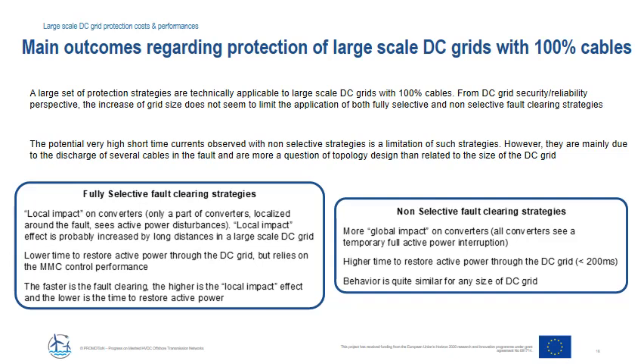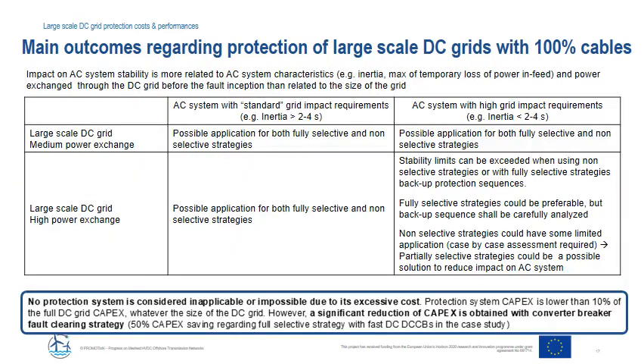Higher times to restore active power through the DC grid, less than 200 milliseconds, as well as a more global impact on converters, that is to say that all converters see a temporary full active power interruption, are observed with non-selective fault clearing strategies. Such behavior is quite independent of the size of the DC grid. The impact on AC system stability is related more to AC system characteristics such as inertia and power exchange through the DC grid before the fault inception than to the size of the grid. As such, it can be expected that both fully selective and non-selective strategies could be applied for the protection of many large-scale DC grid configurations and environments.